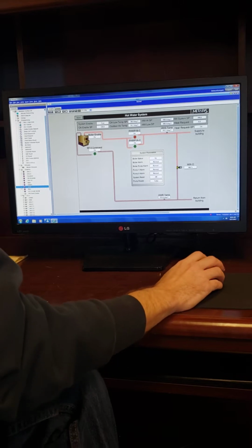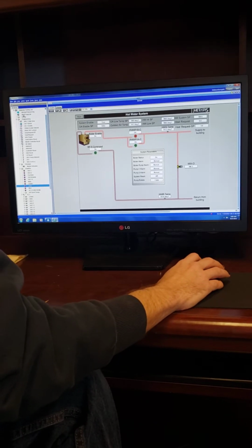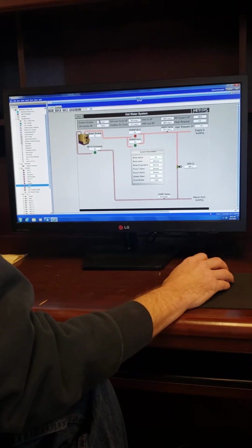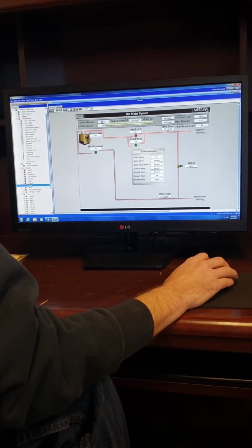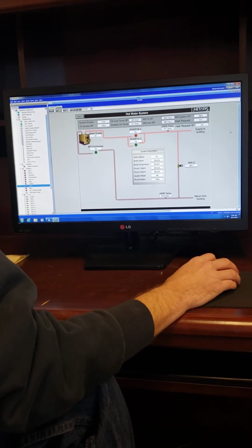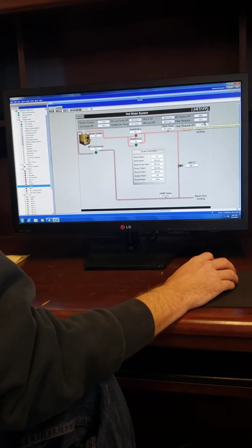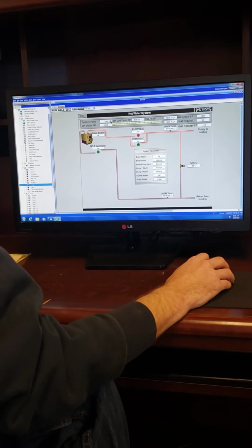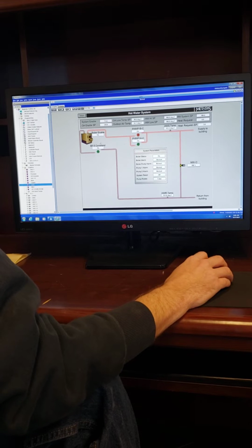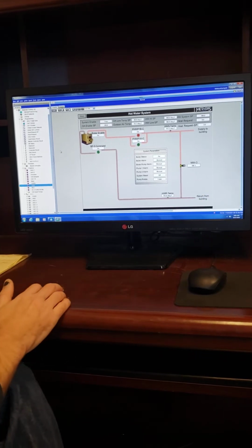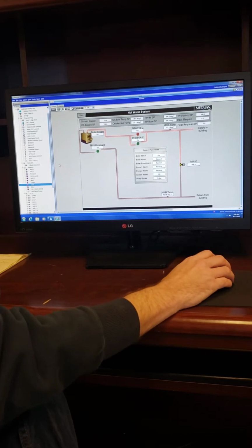I didn't have a full understanding of the way the logic that I'd shown you with all those lines ran. They were turning the system enable, which is only interlocked with the pumps, and the boiler enable on based off of this set point. So now that we have this set point figured out, it's automatically turning the system enable, boiler enable and pump enable on. Everything's running in auto now, so you shouldn't have to worry about overrides or anything. Perfect.